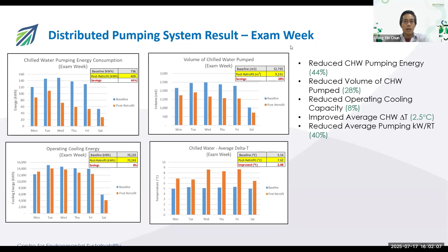So in this case, during the exam week, we see a reduction of the pumping energy of 44%, a reduction of the volume of chilled water pumped by 28%, and a reduction of operating cooling capacity of 8%. There's also an improvement in the delta T, and a reduction in the kilowatt per ton of up to 40%. That's the exam week, which is the full load condition.